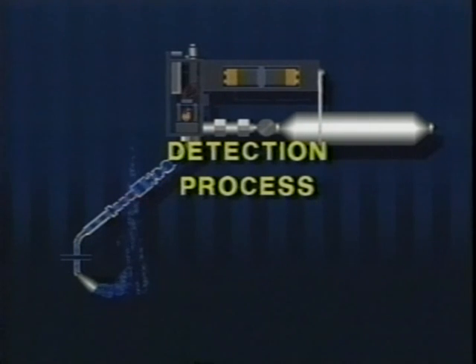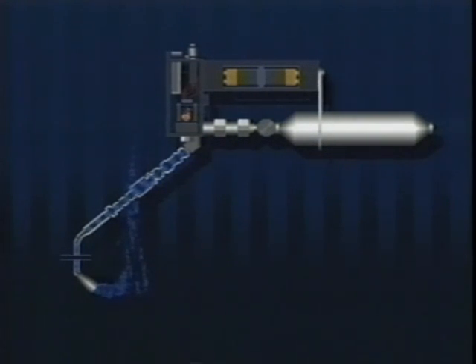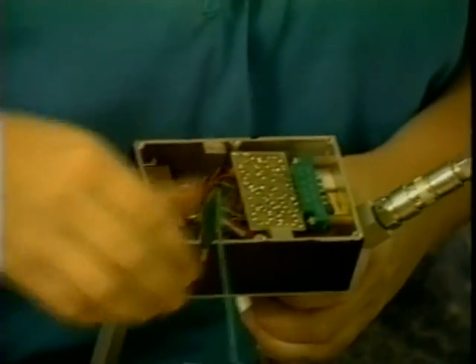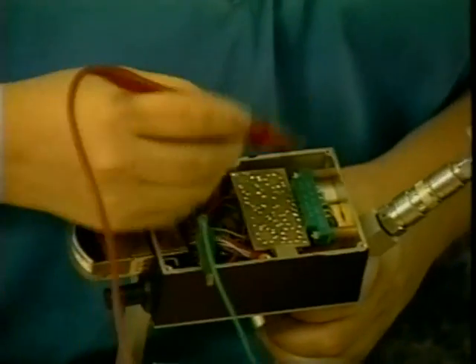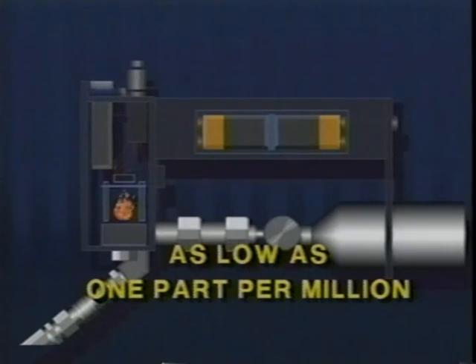In order to detect the presence of gas, the Flame Pack burns a small air sample using a compressed hydrogen-nitrogen mixture as fuel. If hydrocarbons are present, ionization occurs. These ions are then measured by the detection circuitry of the Flame Pack 400. This circuitry is extremely sensitive, detecting hydrocarbon gases at levels as low as 1 part per million.